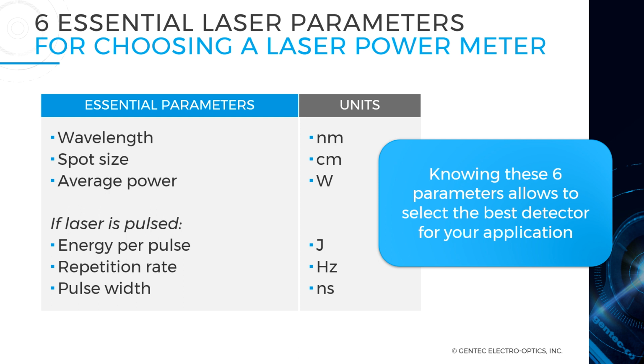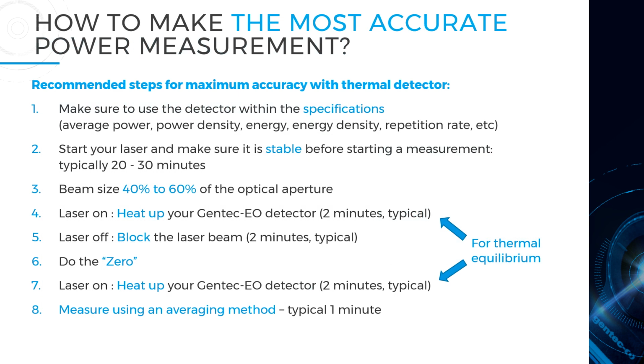Depending on your setup, these parameters might actually be different from what the laser manufacturers provide. Beam size or power, for example, can be affected by optical components used in your setup, by aging parts, or by specific elements to your measurement environment, such as temperature or air circulation. We're happy to discuss this with you so you get the most out of your lasers. And that's the name of the game, right? To get strong measurements to quantify exactly how our lasers behave over time.